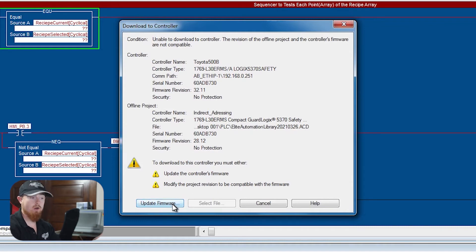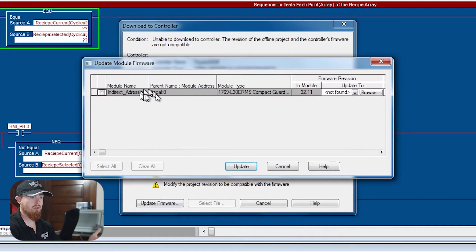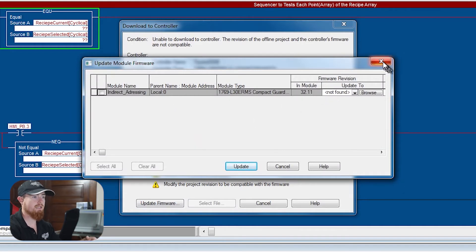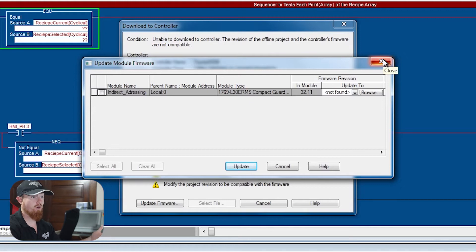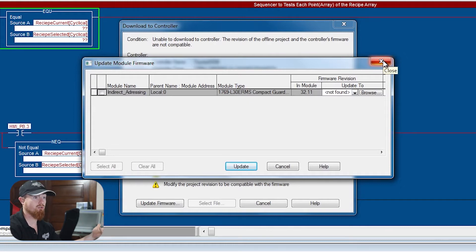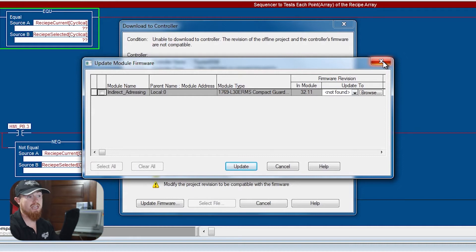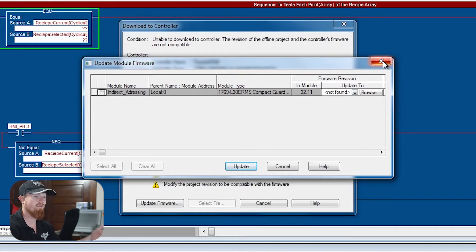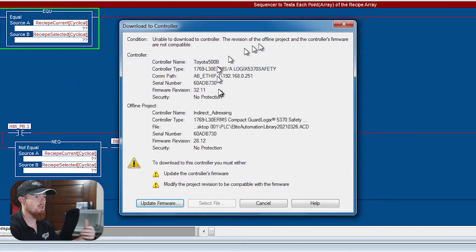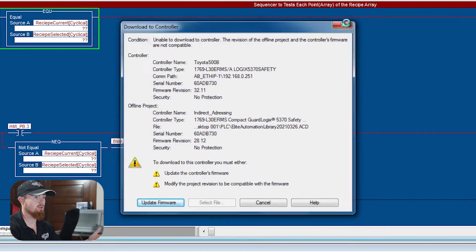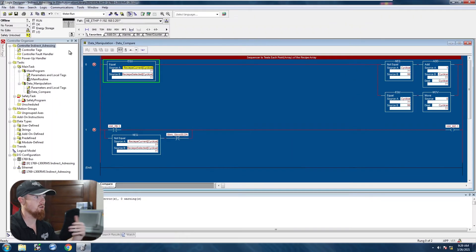So you can update the firmware right here. So come in here and then you get the option to change what firmware you want to run in that PLC. If you don't have the firmware packages, then you're not going to be able to change the firmware of that PLC. And you may even potentially have a PLC that can't handle the certain firmware that you have in your program. So what we're going to do is show you how to change it within the program. So we're going to close that box.